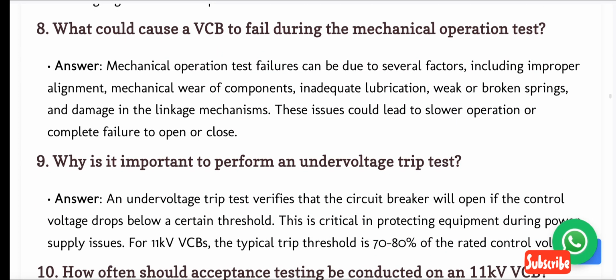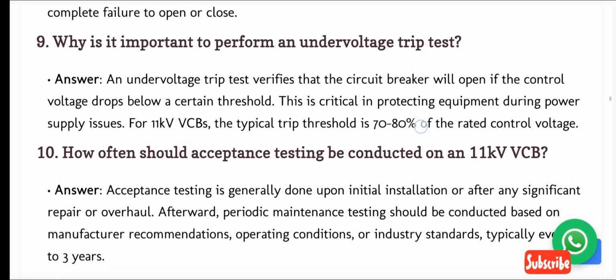8. What could cause a VCB to fail during the mechanical operation test? Answer. Mechanical operation test failures can be due to several factors, including improper alignment, mechanical wear of components, inadequate lubrication, weak or broken springs, and damage in the linkage mechanisms. These issues could lead to slower operation or complete failure to open or close.